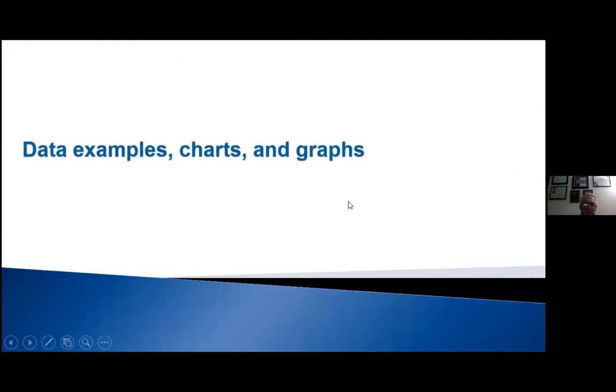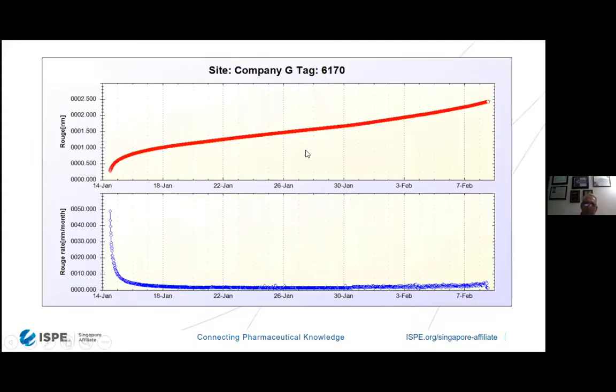Go through some data samples and charts. Over here in red is accumulation of rouge over time. The scale on the left side is in nanometers. So you can see when we introduced this particular unit on January the 14th, it started to accumulate rouge and took about a month, and it went up to around 2 nanometers, 2.5 nanometers, total accumulation over time. The blue line at the bottom, though, is actually the reading every 20 minutes, which shows how the rouge monitor reacts to the water chemistry inside and the temperature and the operations of the water system.